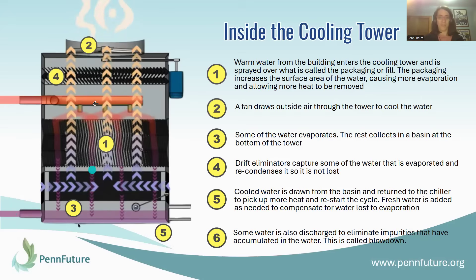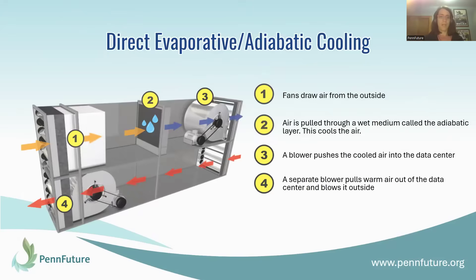Due to evaporation, a portion of the water is lost, so new water gets pumped in to make up for that difference. Also due to the evaporation cycle, impurities can become concentrated in the water, so periodically water needs to be discharged to eliminate these impurities — a process called blowdown. Another system that can use water for cooling is called direct evaporative or adiabatic cooling. In this type of system, a fan draws air from the outside and blows it through a wet medium called the adiabatic layer. This cools the air, which then gets blown into the building, while the other half of the system takes warm air from the building and blows it back outside.